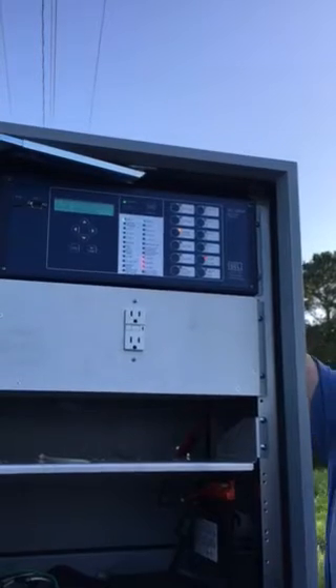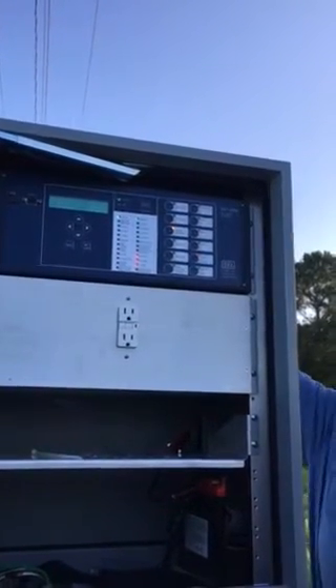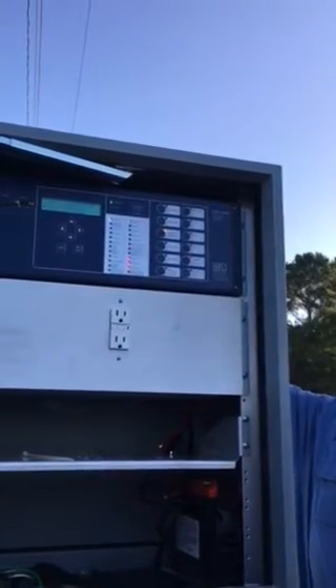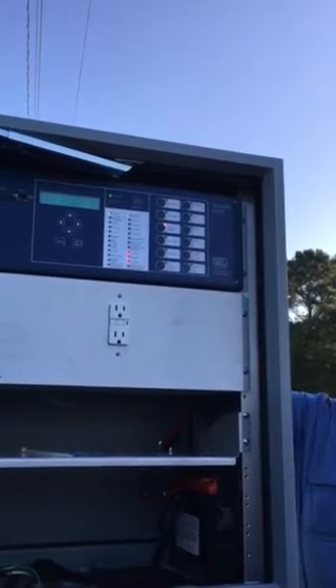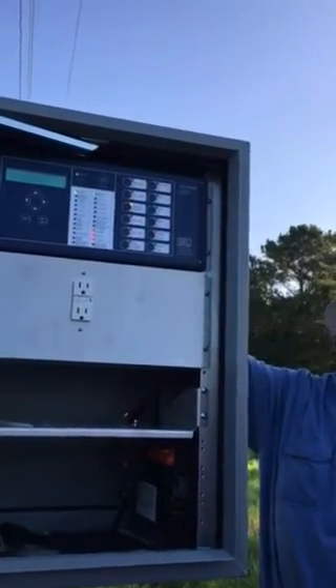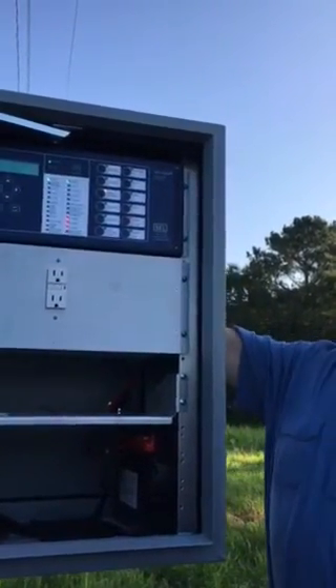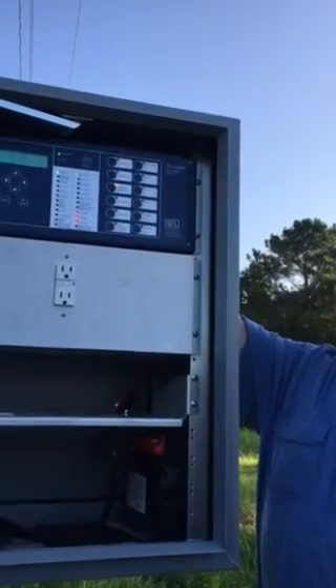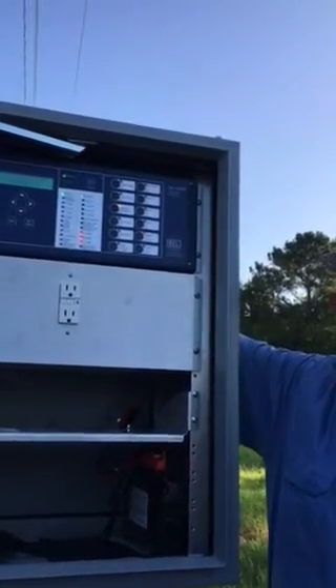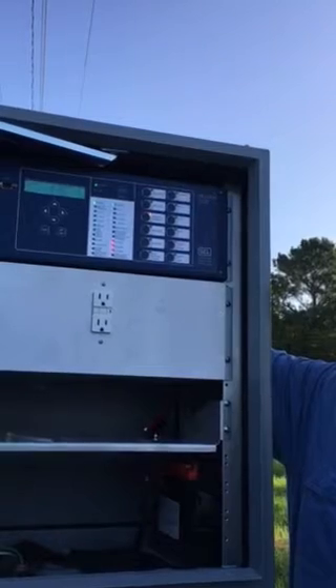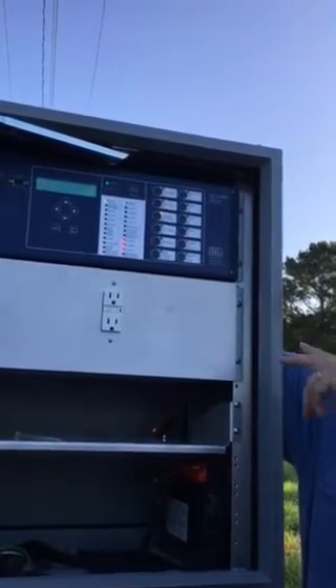The only way you can operate them one at a time, there are some handles up here on this side. You can pull them out. But the only time you would probably ever do that is if something, say lightning, struck it and this whole control cabinet was dead. You can't open and close them just like a regular recloser. And it's always on one shot. If it sees a fault, it doesn't matter if that fault's at the dead end of this circuit. If the amps are high enough, it doesn't matter where it's at, it's taking this solar field off.